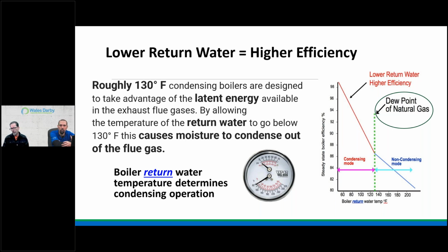So the return water temperature determines condensing operation. The lower you go, the better the opportunity to condense, and therefore your efficiencies always have to go up. Now the chart here shows you that make or break, right? So right side of 130, it's non-condensing, and the left side is condensing.